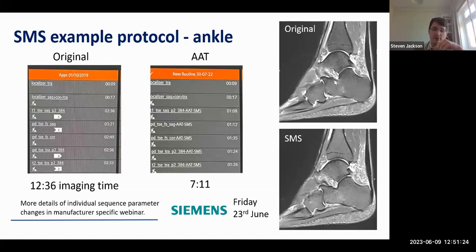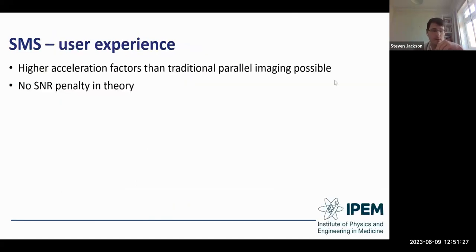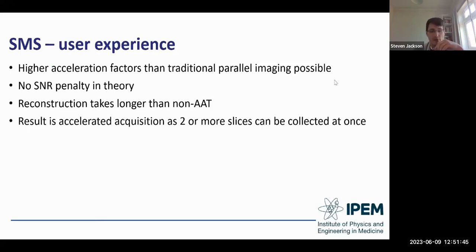An example protocol: an original non-AAT ankle protocol came in at around 12 and a half minutes. An AAT version using only the SMS TSE technology on a Siemens scanner reduced that time by around five minutes, with comparable image quality. More details of individual parameter changes will be in the third webinar on the 23rd of June. One consideration: reconstruction takes a little bit longer than non-AAT sequences, which may require rejigging your protocol order — you don't want a long-reconstructing sequence last, as you'll be waiting before you can decide whether to bring the patient off the table.